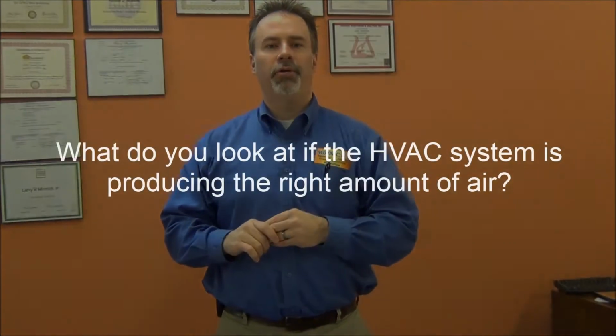Then we go in with what's called a flow hood that measures the airflow that you're actually receiving in each room. And then we can see what's happening within each space to properly heat and cool that space, as well as your returns, measuring all your returns, making sure you have enough return on each level of the floor. We find there's a lot of return being pulled in the basement and not enough supply, so all the air is being pulled down into the basement, and that can be why basements are so cold, along with duct leakage and so forth.